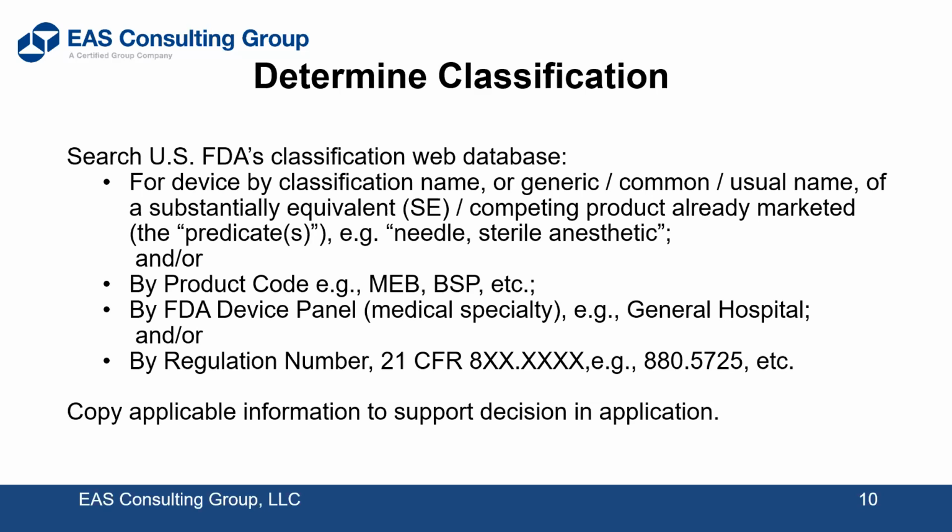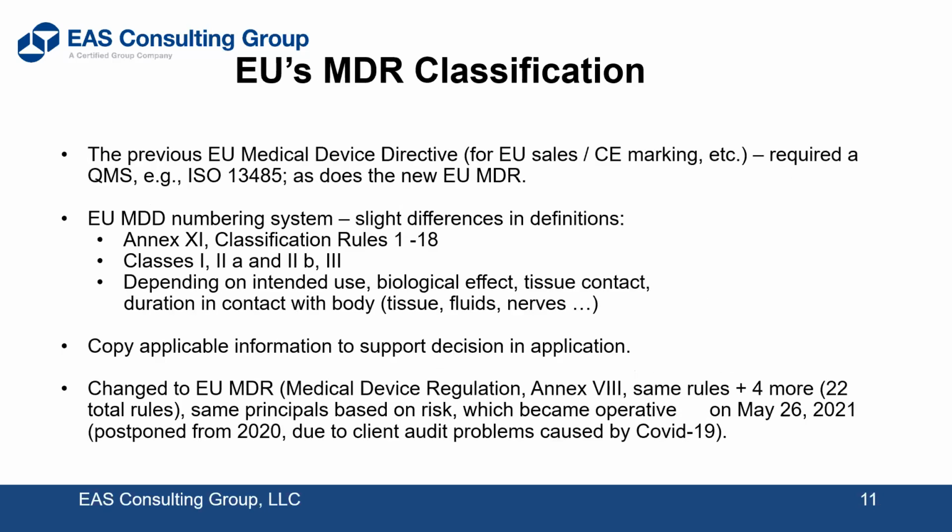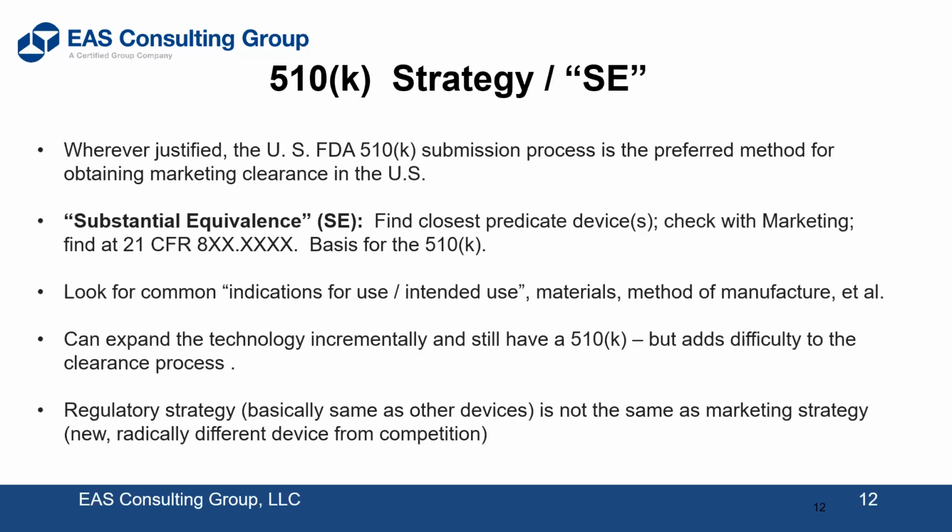And the regulation will also tell you which device panel will be reviewing your product when you submit it under the 510K. As I mentioned, the medical device regulation overseas has a different classification program. We're not going to get into that, but just be aware of the difference, and I've covered it a little bit. The key purpose of a 510K is to prove your product is substantially equivalent to a product already in the marketplace. So this brings you to an issue.